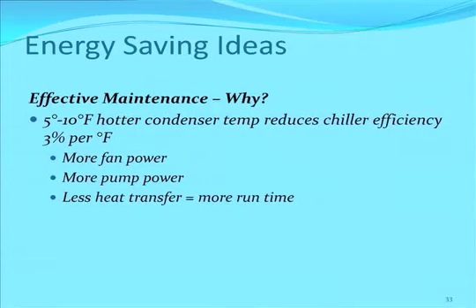Why do I care about maintenance? Why do you care about maintenance? Your cooling tower is a heat transfer device. Anything that you can do to keep it operating in stellar performance is going to be better for you. Anything where you slack off on allowing your heat transfer device to transfer heat is going to cost you energy and can cost you water as well. The fans have to work harder, the pumps have to work harder, and they have to run longer.